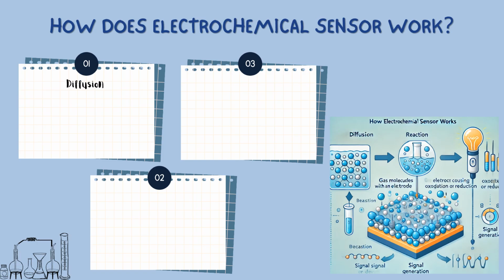The first step is diffusion. This is a process where the target gas or substance moves through the gas permeable membrane of the sensor. The membrane is designed to allow only specific molecules, such as oxygen or carbon monoxide, while blocking other unwanted substances. This step is important because it helps the sensor focus on detecting the correct analyte. The gas molecules that successfully pass through the membrane reach the electrode surface, where the next step begins.